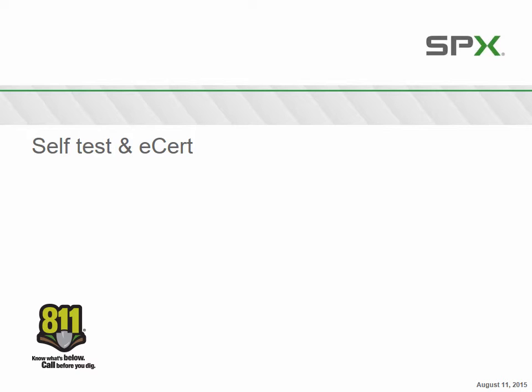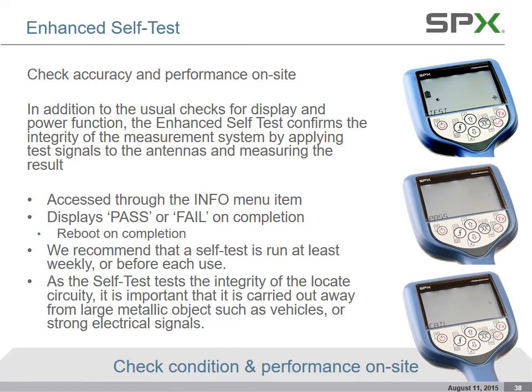The self-test and the eCert are new, well, the self-test is certainly new on this unit. The self-test gives you a pass or a fail upon completion, and it's mainly testing the integrity of the circuitry. It does not test for the calibration, for the accuracy of the depth and the locate. It's mainly telling you that everything in there is working and the circuits are in good shape.